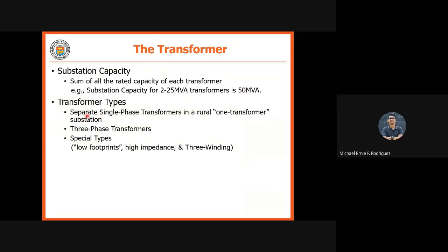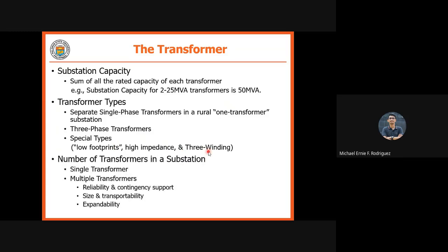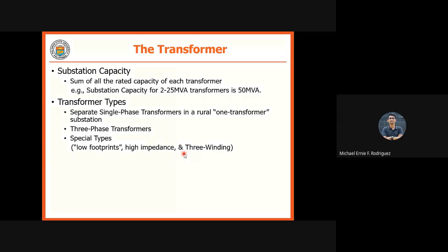Separate single-phase transformers in a rural one-transformer substation. Okay? These single-phase transformers are not commonly used. Usually, what we use are three-phase transformers. Then we have special types: low footprints, high impedance, and three-winding. Three-winding, if you saw it earlier, that is a three-winding, three circles. So, delta, Y, delta. Three-winding.